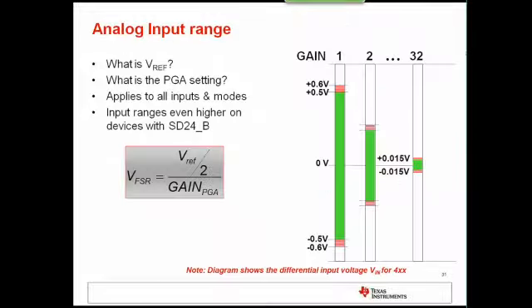There's a maximum range that the ADCs can sense, and this is defined by the full scale voltage. On the 4XX family, this is calculated by taking the reference voltage, dividing that by 2, and dividing that by the PGA gain. On the 6XX family, you have an even higher full scale range, because the actual equation is VREF over the programmable gain amplifier.